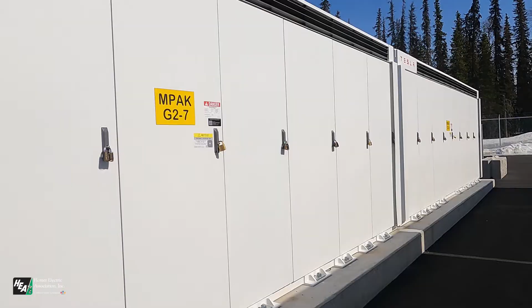It probably goes without saying that such a small grid as the one we have along the road system in Alaska is much more sensitive to frequency excursions. In effect, these are load changes, generator trips, or transmission interruptions than a much larger or more interconnected system like that in the lower 48.